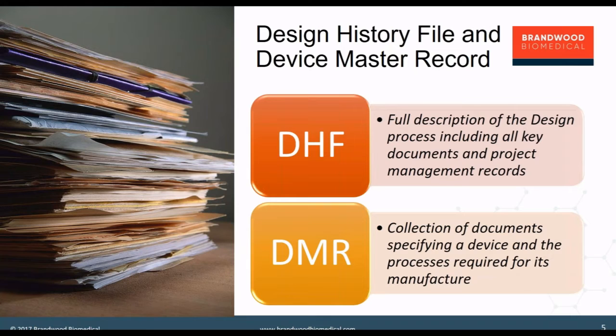So the first concept which is presented in those documents is the design history file. The design history file is the collection of the documents which provide a full description of the design process, including all the key documents and project management records. So that's essentially all of the history of your product development, both for the initial release but also as part of the product lifecycle.